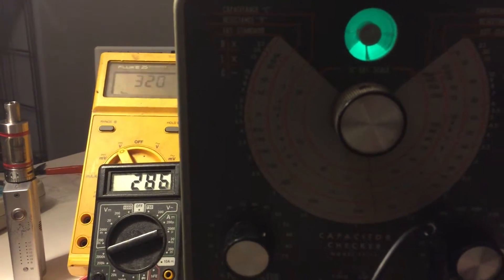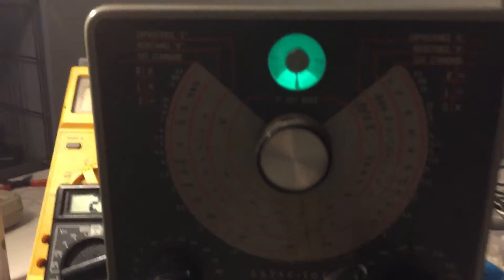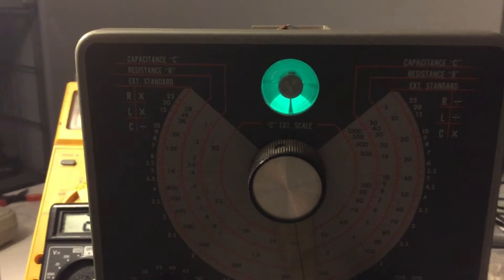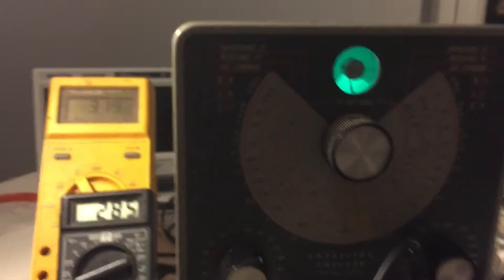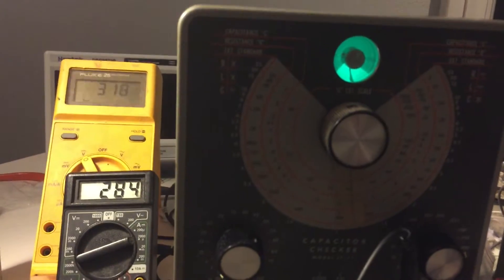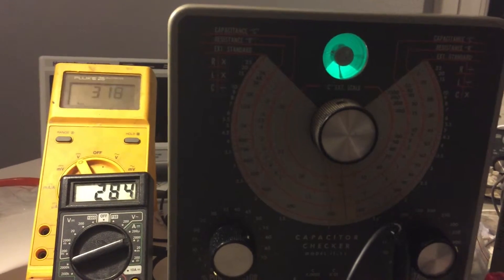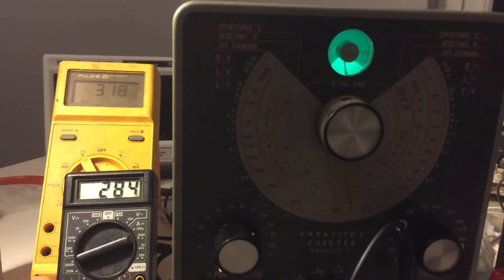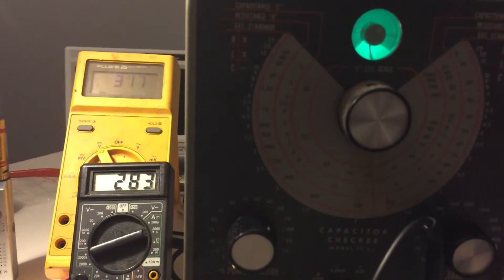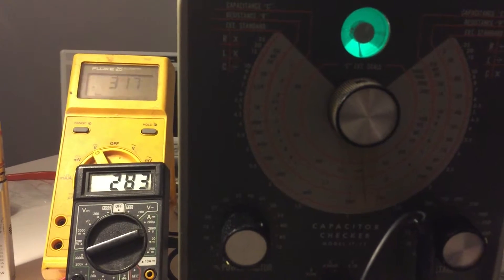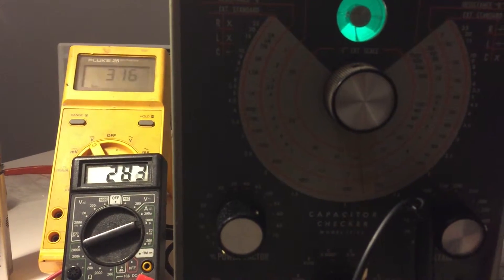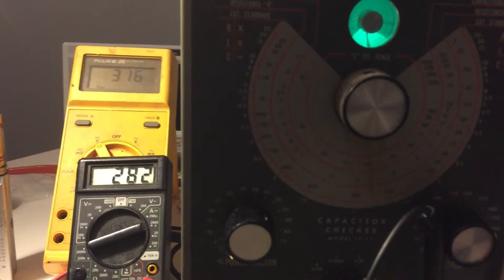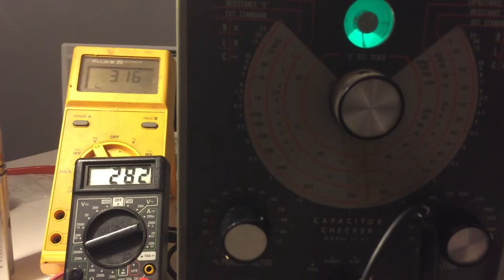So right now there's a significant voltage drop that's being seen on the Fluke meter. And at 400 we're actually seeing 317 because the circuits be loading down and it's taking a very long time to recover. It may actually go in the other direction but these are the capacitors that you do not want in a circuit.